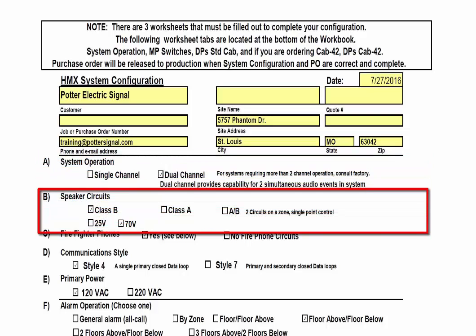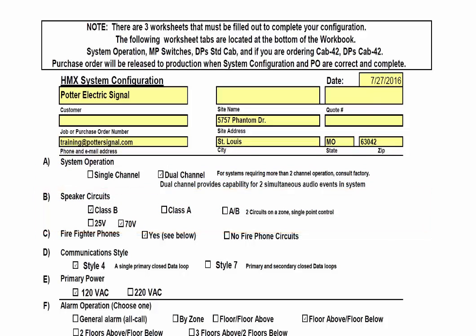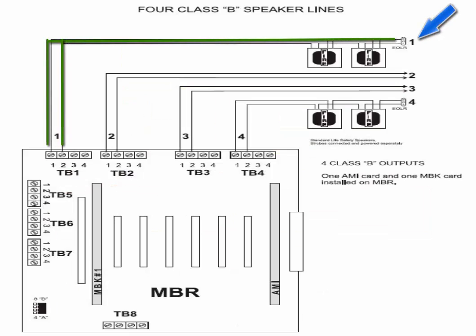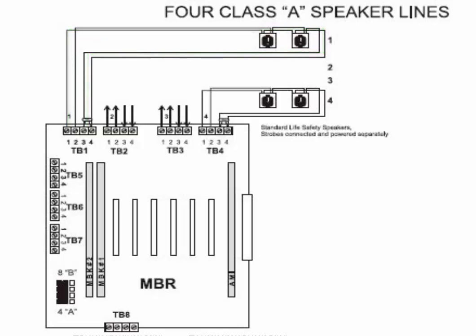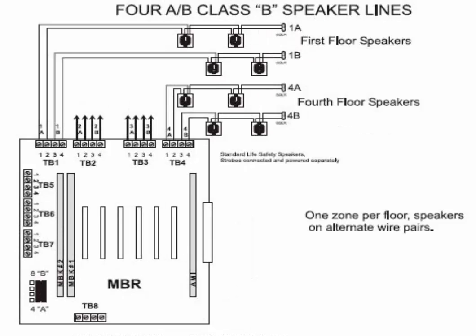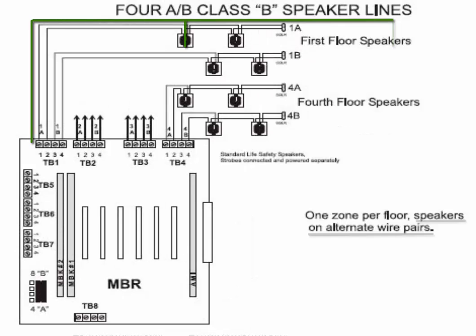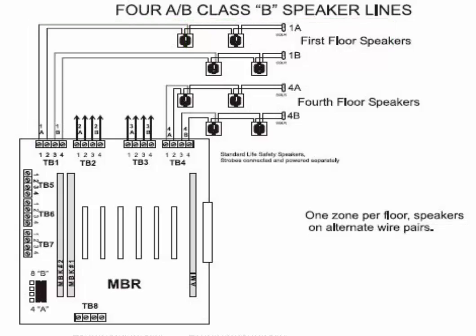In this section, the wiring style and voltage for the speaker circuits is defined. Class B speaker circuits consist of two wires with an end-of-line resistor which is installed at the last speaker. Class A speaker circuits require the circuit to return back to the distributed panel after the last speaker. Class AB speaker schemes are only selected when there is a requirement for every other speaker that is installed to be on a different circuit.